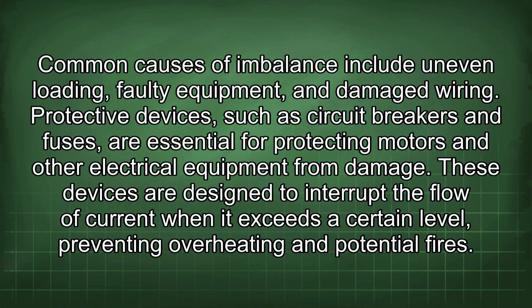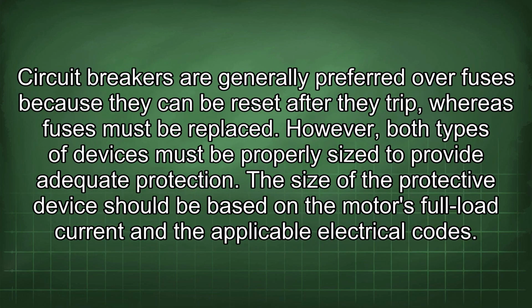Protective devices such as circuit breakers and fuses are essential for protecting motors and other electrical equipment from damage. These devices are designed to interrupt the flow of current when it exceeds a certain level, preventing overheating and potential fires. Circuit breakers are generally preferred over fuses because they can be reset after they trip, whereas fuses must be replaced. However, both types of devices must be properly sized to provide adequate protection.